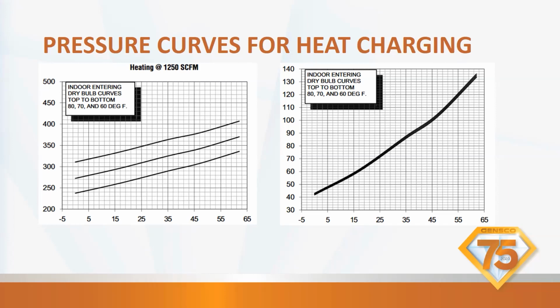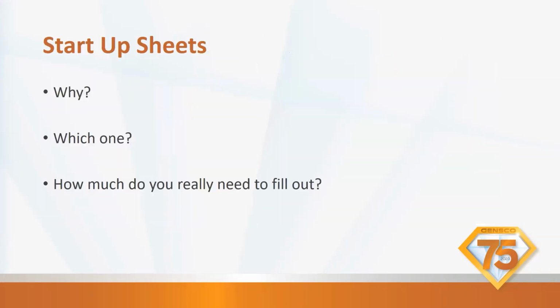Basically, you're looking at the high side, you're looking at the subcooling, and that's going to get you close until you can come back in the summer and do a true subcooling check in air conditioning mode. Startup sheets. Make sure you're doing startup sheets when you're doing an install.